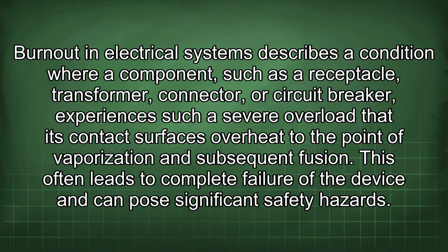Burnout in electrical systems describes a condition where a component such as a receptacle, transformer, connector, or circuit breaker experiences such a severe overload that its contact surfaces overheat to the point of vaporization and subsequent fusion. This often leads to complete failure of the device and can pose significant safety hazards.